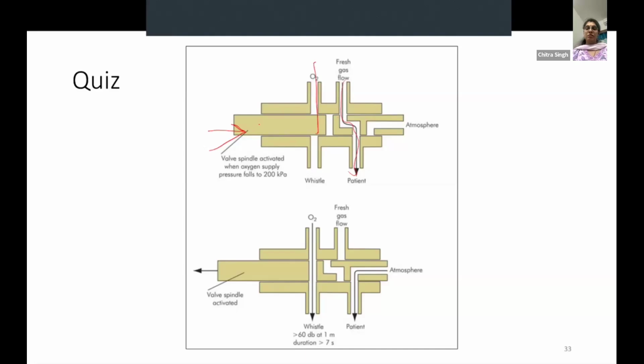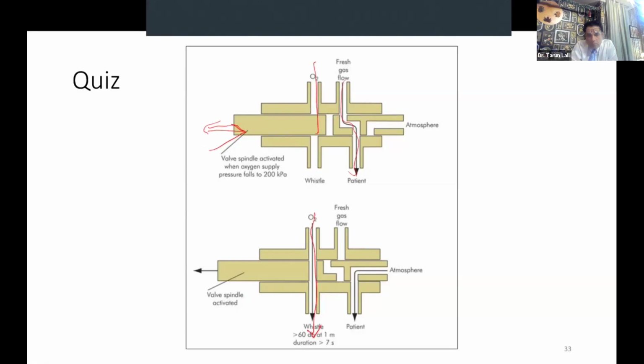As oxygen pressure falls, this spindle moves to the left because oxygen pressure is no longer able to counter the pressure of the spring. The spindle moving to the left provides a channel for oxygen to flow through the oxygen port, and this results in a whistling sound which should be audible at more than 60 decibels for more than 7 seconds. This used to be an oxygen hypoxia prevention device in the older machines, which is now replaced by the low oxygen alarm in our machines.